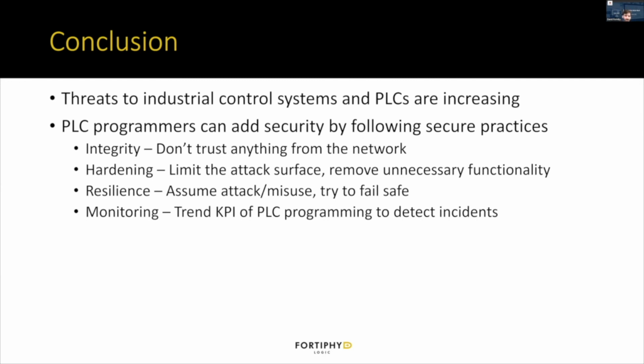Adding resilience to the PLC by assuming that things are going to go wrong, trying to fail safe, and trying to mitigate damage to the process. And finally, adding monitoring, trending essentially the KPIs of the PLC programming itself, to help detect incidents in the control system.